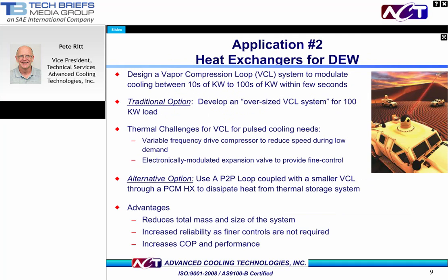For our next example, we'll look at a heat exchanger design for directed energy weapons, DEW. These systems typically have multiple parallel electronic boards that have tight temperature uniformity requirements. Further, it is desirable to have the thermal management for these systems to be as lightweight and compact as possible. The traditional solution has been to design and build a vapor compression loop to handle the maximum heat load, even though that heat load is not always present in operation of these pulse devices.